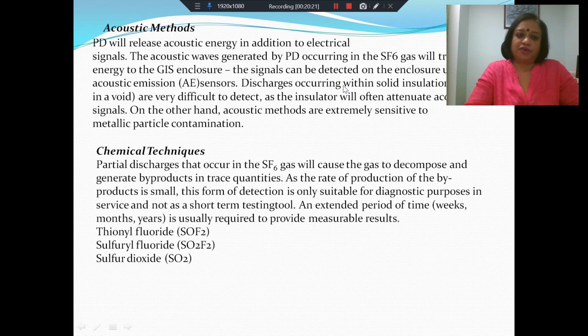Next, of course, we have acoustic methods, where acoustic energy is released at the source of the PD. These acoustic waves travel through the SF6 gas and reach the GIS enclosure. At the enclosure, the metal begins to vibrate, and if you place acceleration sensors, accelerometers or displacement sensors on the outside of the GIS enclosure, they can pick up the small vibrations of the enclosure. Discharges occurring within the solid insulation inside a GIS are very difficult to detect because the acoustic signal will have to propagate not through SF6 gas but through solid materials, and some solids might be opaque to acoustic waves, so they will not allow acoustic waves to travel through, or there might be considerable attenuation.